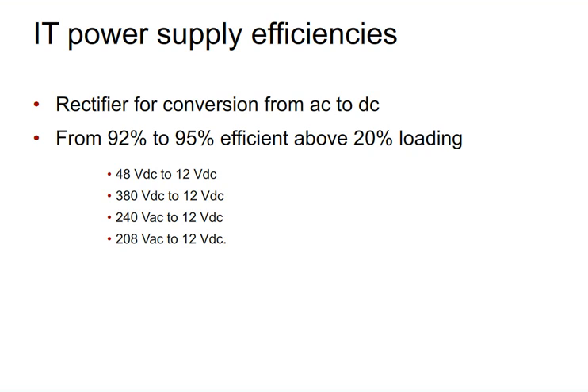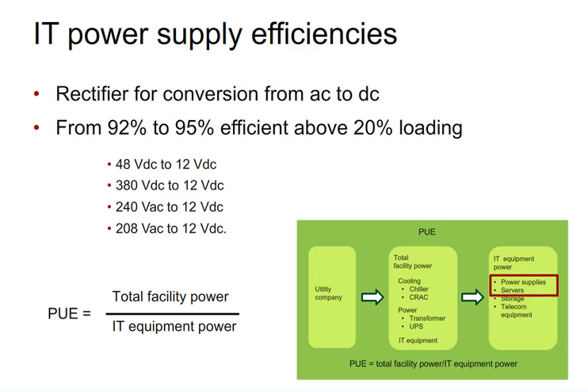The IT power supply also has losses — a rectifier from AC to DC and some transformation, with about 92-93% efficiency depending on whether it's 380 V DC or 240 V AC. Interestingly, the IT power supply is in the denominator of the PUE equation, so inefficient servers would actually improve your PUE ratio while hurting your overall energy use — which illustrates a key limitation of PUE as a metric.